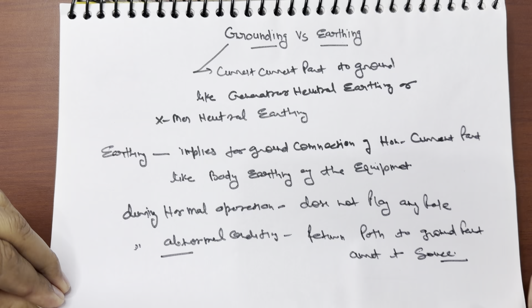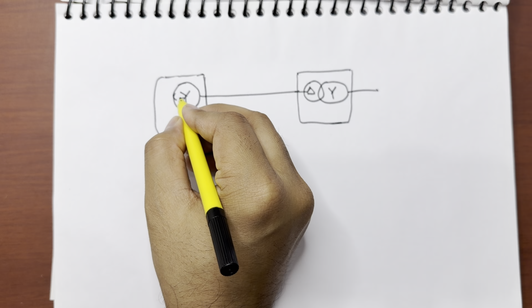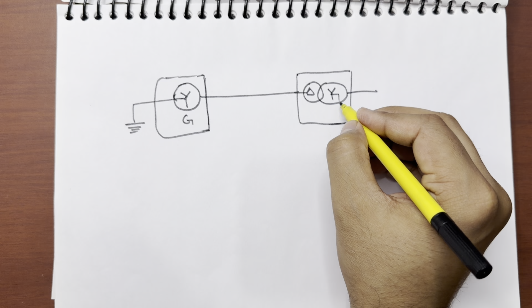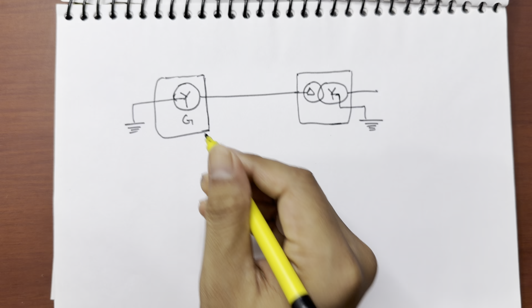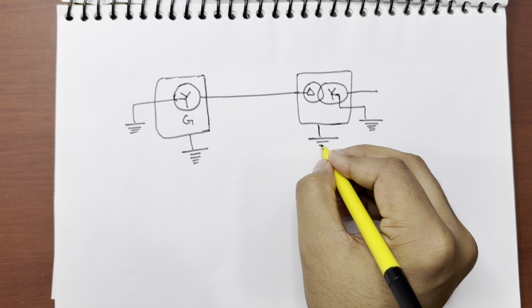So let me give you an example of system earthing and grounding. Let us consider this is my generator, a star connected generator, and this is connected to a transformer. Primary is delta and secondary is star. This is the enclosure, or you can say frame of the generator, and this is the enclosure of the transformer. This generator neutral is grounded. This transformer neutral is also grounded, and the enclosures of the transformer and generator are also grounded. Similarly, the transformer neutral is also grounded.